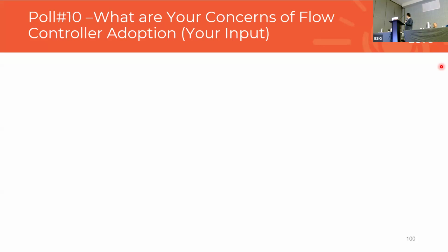We have seen more urban applications that did have imbalance want this device. The one challenge in more urban applications is that it is a pad mounted device, so siting it can be a little bit more challenging in those areas. We've seen some utilities make it work, where they say, we want to try to put it out here, and they have found locations for it. So that's been great. But as you get more into urban systems, from my experience, oftentimes they're a little bit more balanced. They're built shorter, more robust, and you don't see as many application benefits as you do on some of the others that are a little bit more rural.